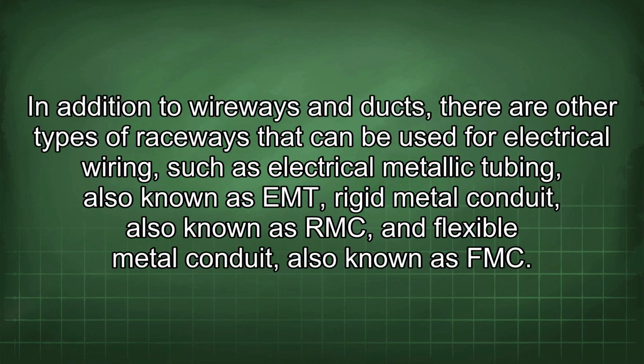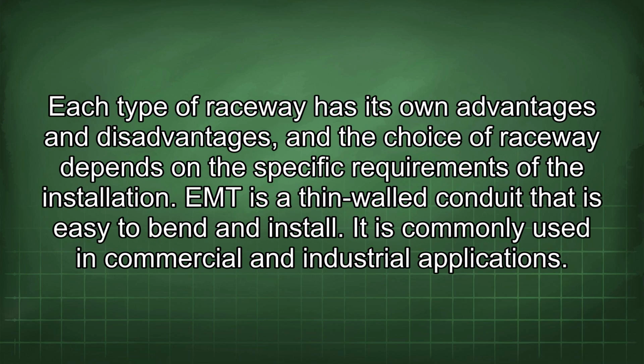In addition to wireways and ducts, there are other types of raceways that can be used for electrical wiring, such as electrical metallic tubing, also known as EMT, rigid metal conduit, also known as RMC, and flexible metal conduit, also known as FMC. Each type of raceway has its own advantages and disadvantages, and the choice of raceway depends on the specific requirements of the installation.